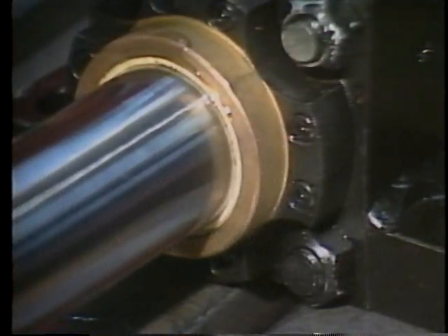When side loading is severe enough, the piston tries to stroke at an angle to the barrel instead of moving parallel to the walls, and it can bind inside the cylinder. Even a small amount of side loading should be avoided because it wears out the cylinder packing and creates leakage. Now let's see what can be checked just as quickly at the pump and reservoir.